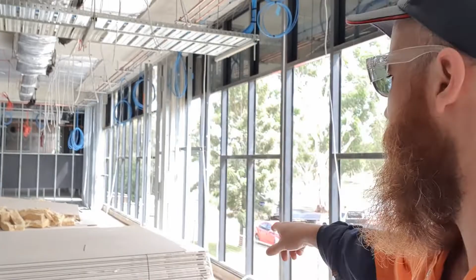Had a massive muck around this morning trying to work out whether these pendant arms need to be on a body protected RCD or not. But been through the whole thing. It's a specified fitting designed for hospitals, so it's actually got a body protection rating on the arm, which is good. That means all we need to do is supply an outlet in the roof. There's a transformer on the light itself, and then we can just have it on a 30 milliamp RCD back in the switchboard, rather than this 10 milliamp RCD mounted on the wall in the body protection room. So that's a win.